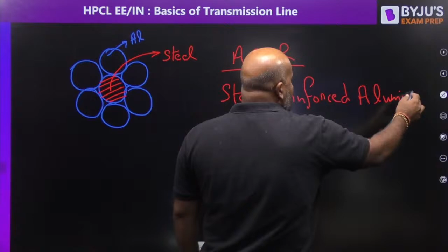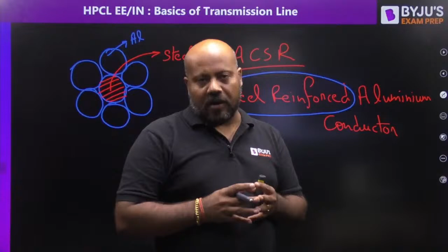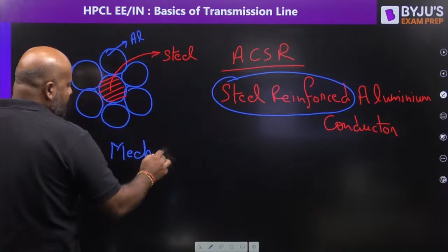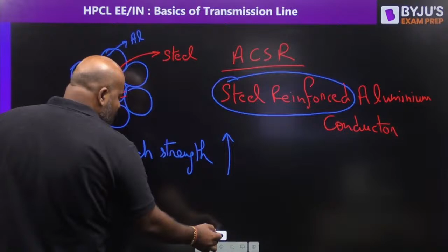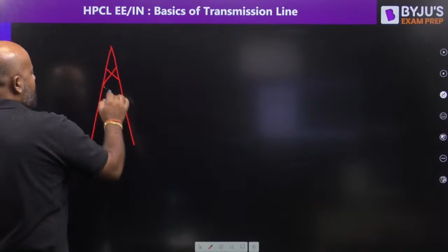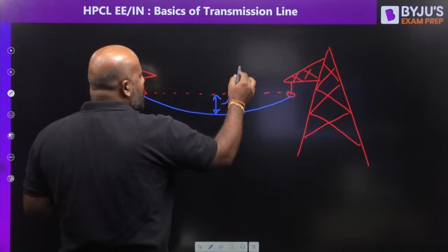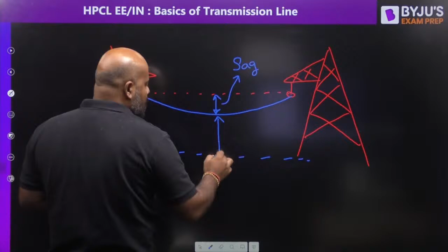Why are you using it? You are using steel reinforced in order to increase the mechanical strength of the conductor, because using the steel strand is going to give mechanical strength to your conductor. And what is the consequence of that? Suppose mechanical strength has been increased. So what is the consequence? Suppose you have this type of construction, and this is your conductor, there is going to be some sag, yes or no? This drop in the conductor we define as sag, and if this is your ground, then this distance from the ground we define as ground clearance.